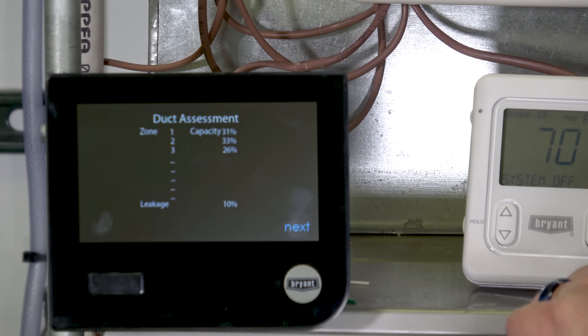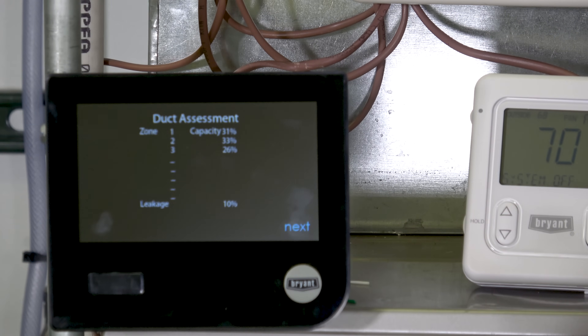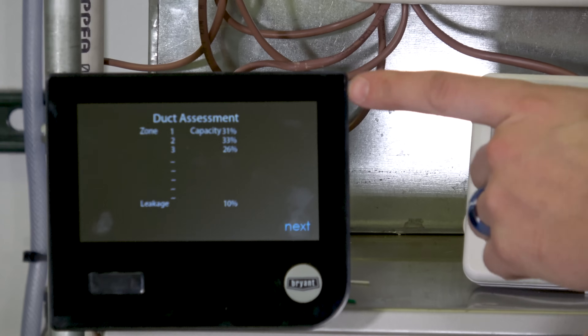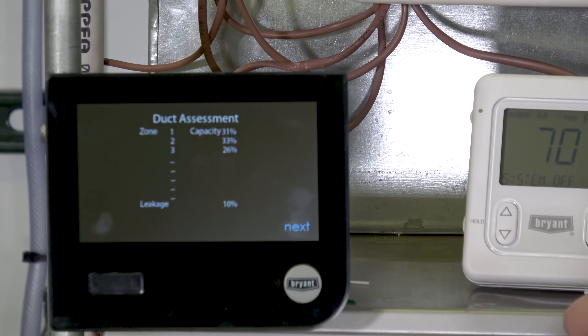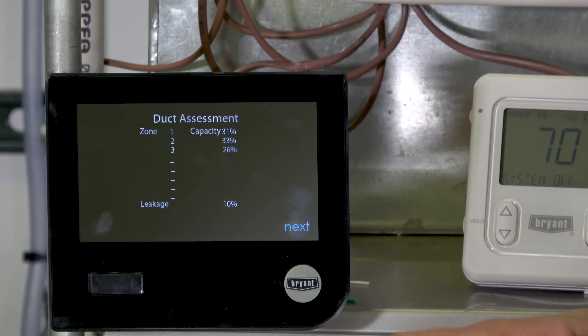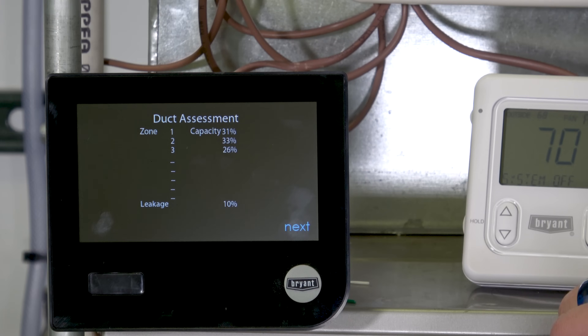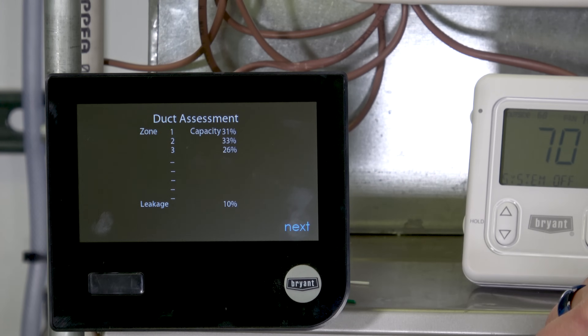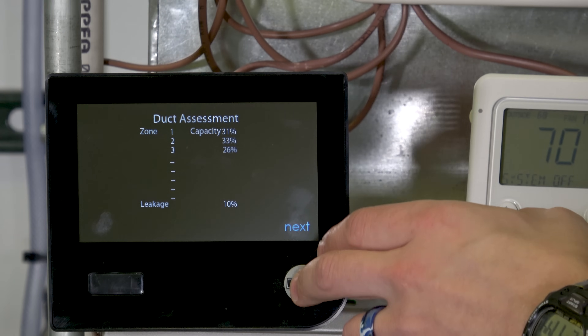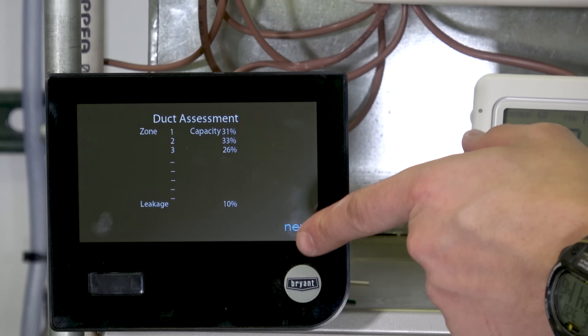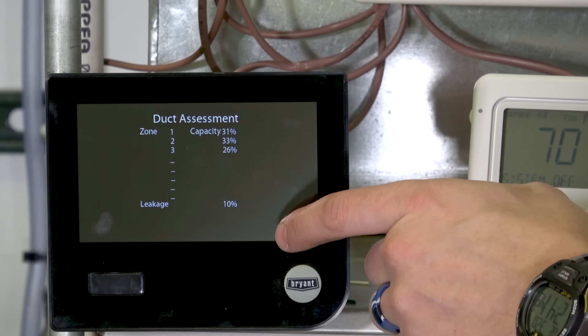The duct assessment report came back. Our zones are pretty equally sized: 31%, 33%, and 26%. It also tested with all dampers closed to measure system leakage, which was 10% — actually really low. Most of the time you see 30–40% leakage, but in this case our duct system is tiny — about five feet on the main run and literally no duct on the two other zones. That wouldn't comply with code in a real house, but we're in a lab.